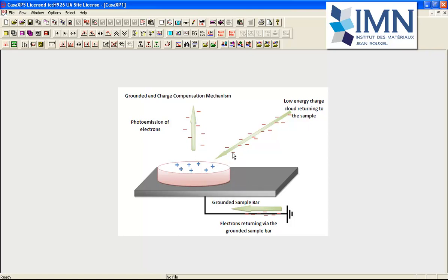We must have charge compensation for two reasons. First, if we allow charge to continuously build up, the energy that we would like to characterize these electrons by in terms of binding energy will alter by virtue of the fact that these electrons will be retarded by different potentials at the surface over time.